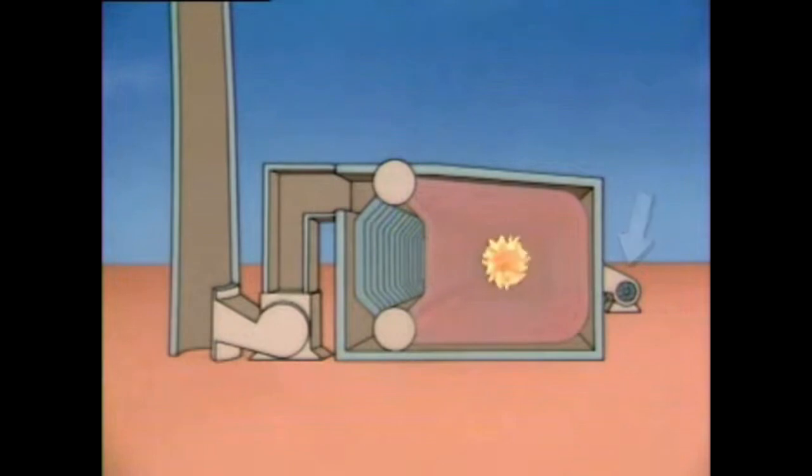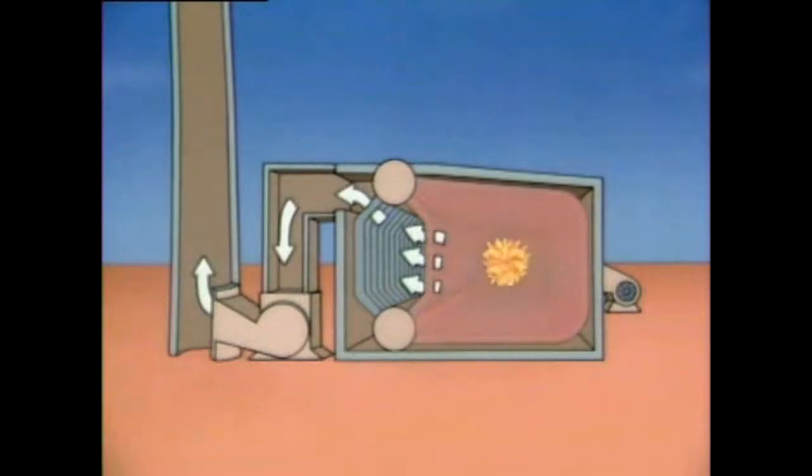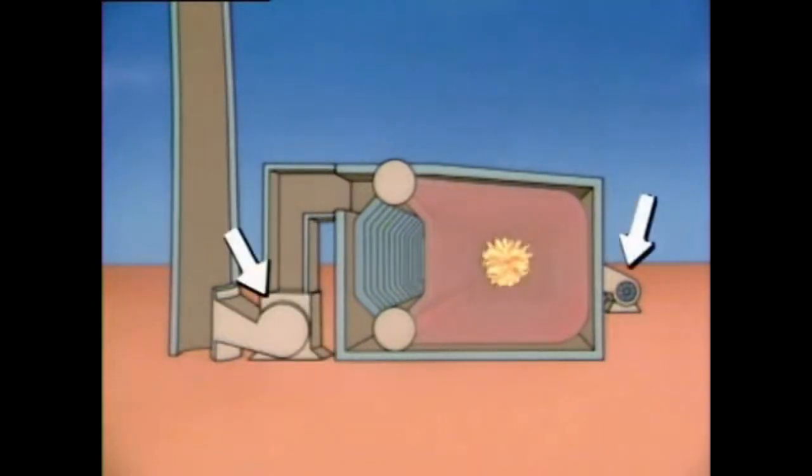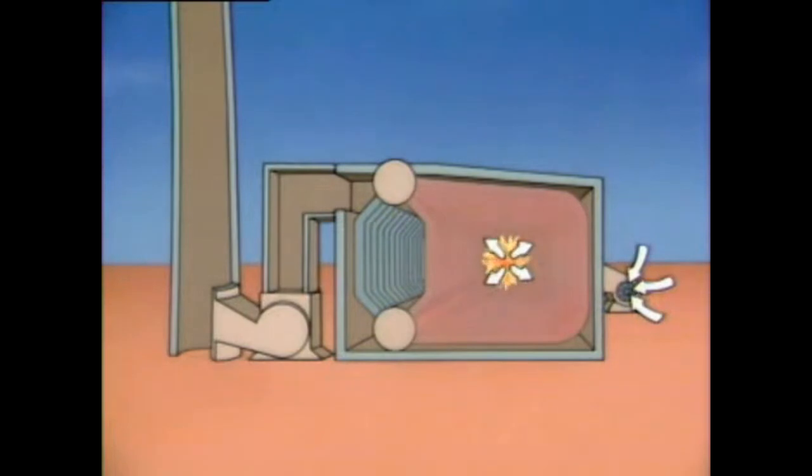A forced draft fan draws air from outside the boiler and forces it through the burner into the combustion area. Induced draft fans create draft by drawing combustion gases from the boiler. Many boilers operate with only a forced draft fan. However, some boilers need both types to provide the proper draft. For example, in this boiler, the forced draft fan supplies air to the burner. Then, the induced draft fan draws out the hot combustion gases.